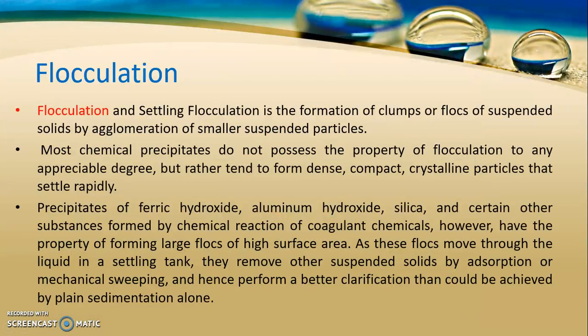Flocculation is the formation of clumps or flocs of suspended solids by agglomeration of smaller suspended particles. Most chemical precipitates do not possess the property of flocculation to any appreciable degree, but rather tend to form dense compact crystalline particles that settle rapidly. However, precipitates such as ferric hydroxide, aluminum hydroxide, silica, and certain other substances formed by chemical reaction with coagulants have the property of forming larger flocs with high surface area.